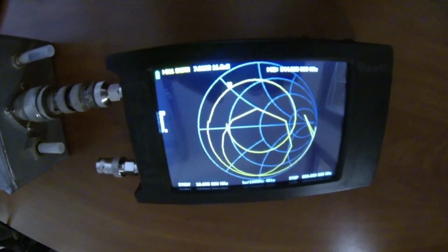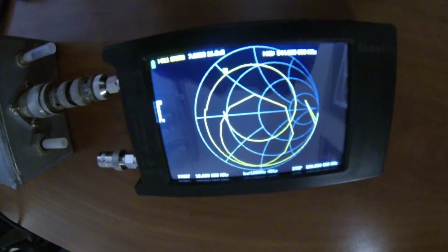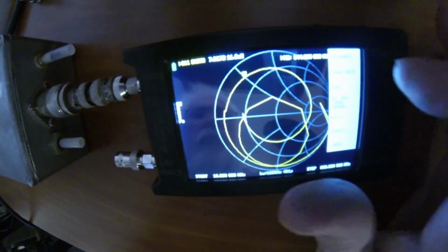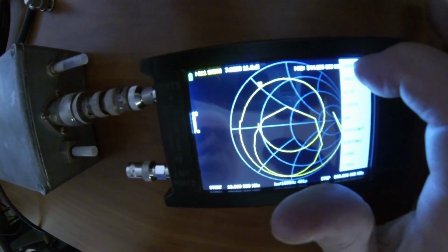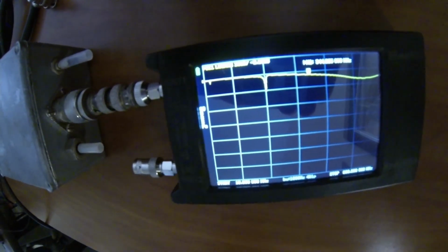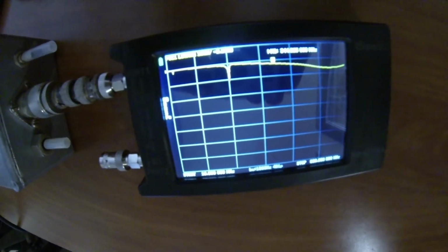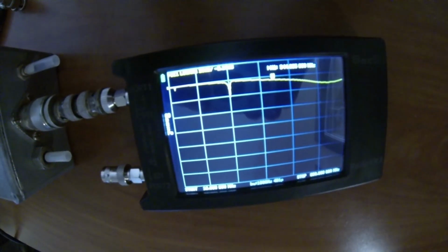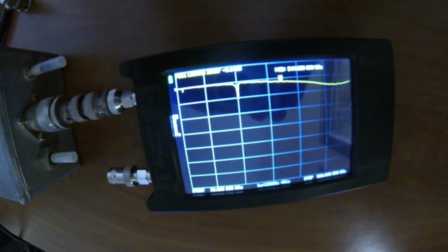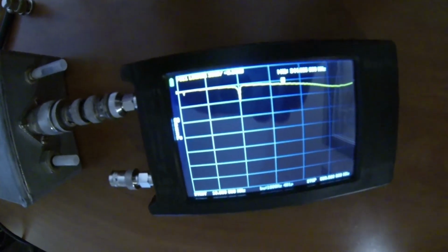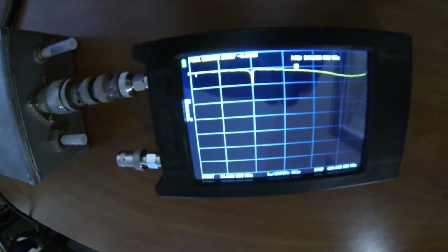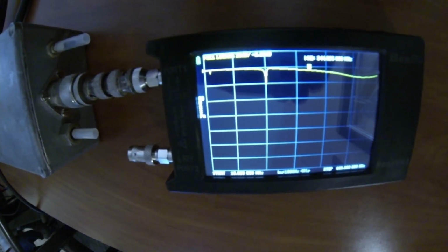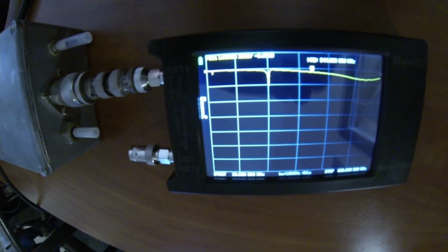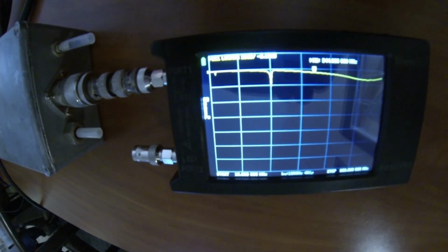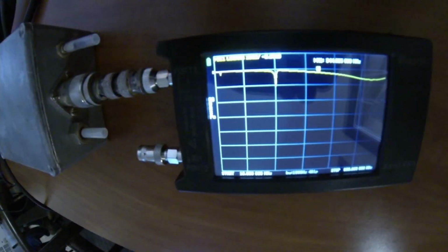What I'm going to do here is switch this right now to a different display. We're going to change the display format to log mag. So we're looking at the reflection loss, the return loss, and there's a dip over here. These are 10 decibels per division here. This line up here is 0, which is perfectly reflecting. And you can see over here at this frequency, there's a dip. That means it's absorbing there. It's tuned, give or take, to that frequency.